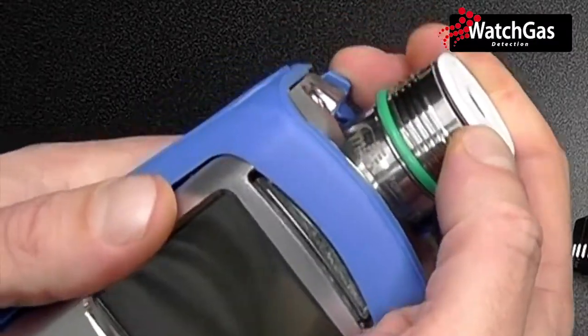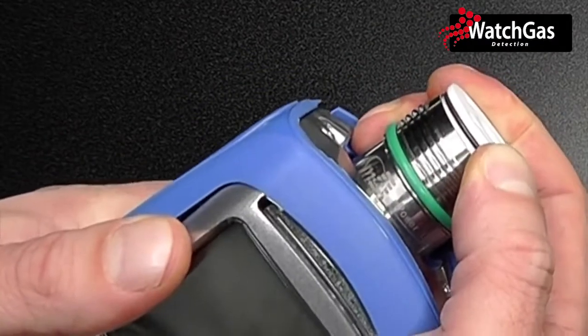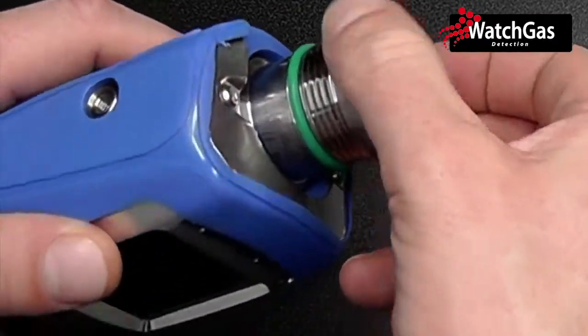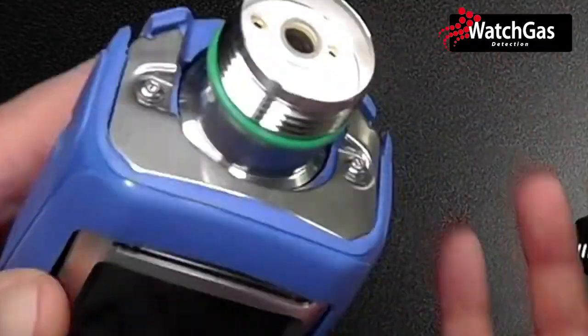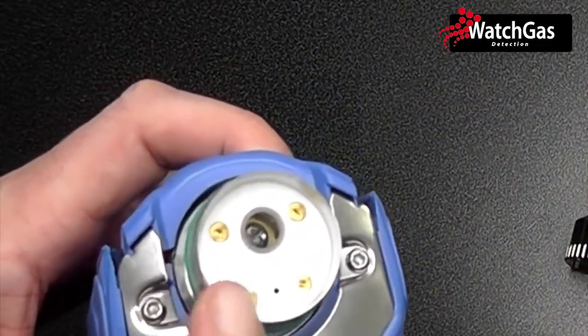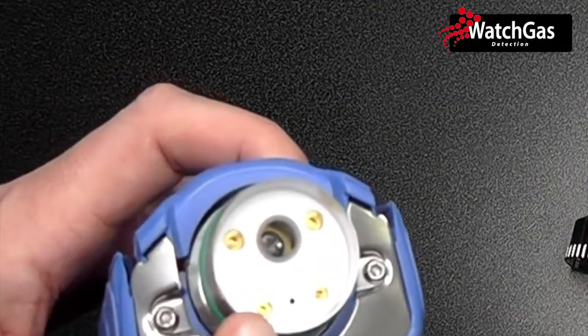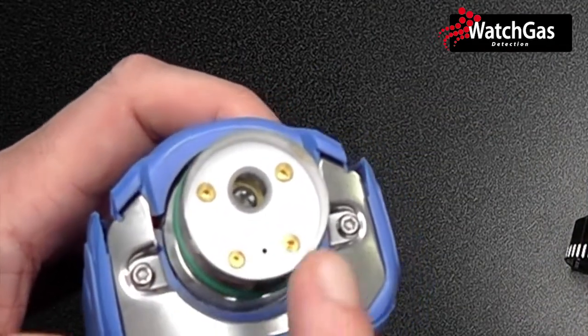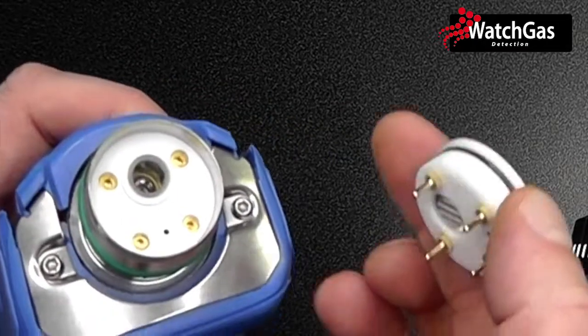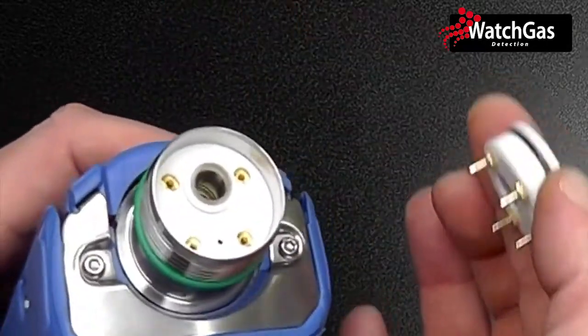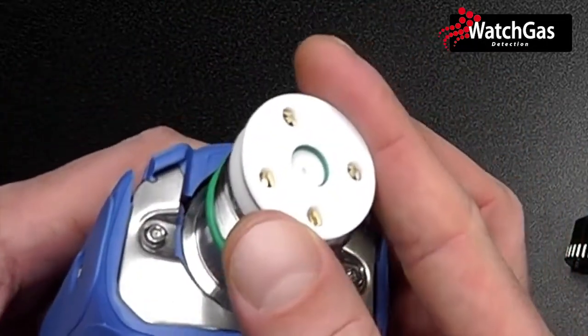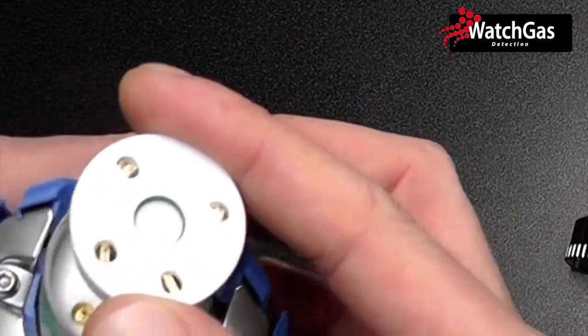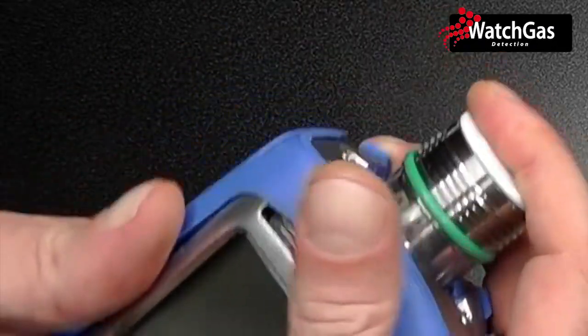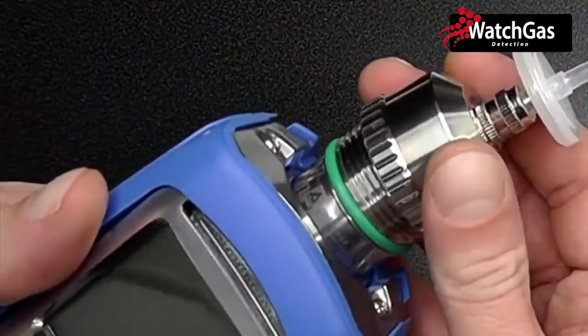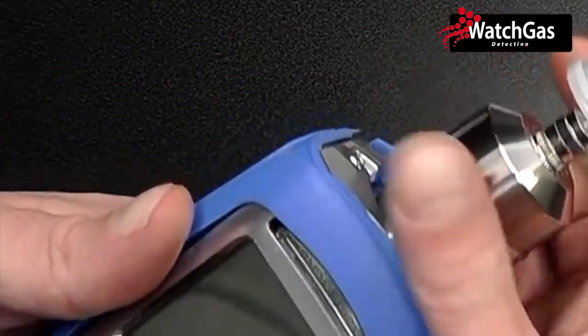So to remove the sensor housing is a relatively simple procedure. We just have to lever off the top section, being quite careful, and then you can pull off and we can see the standard lamp exposed. The unit is also supplied with a cleaning kit for cleaning the lamps, should you need to do anything, but other than that, this section should remain closed. The lamp is right at the front end of operation, so it means that you get very swift response to gases and a very quick clear down time, unlike some other VOC monitors on the market. And then to reattach, screw in position.